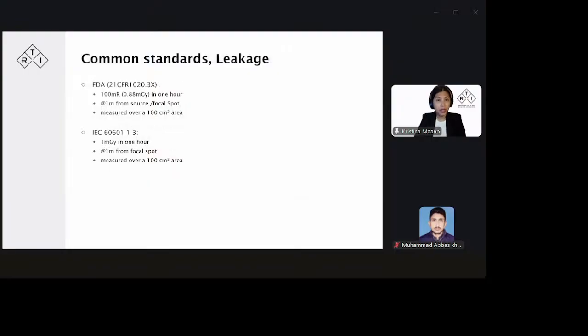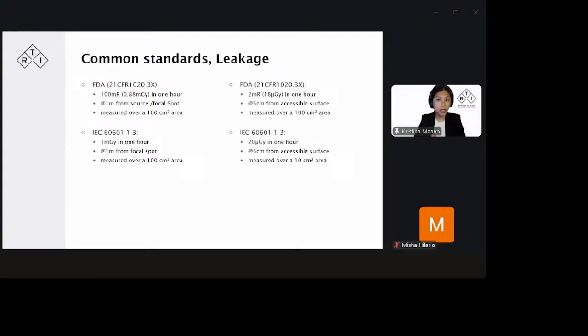All right, so there are standards for leakage evaluation, and two that we are very familiar with, and we have seen them adopted all around the world. First, the IEC, the International Electrotechnical Commission, which says that 1 milligray in 1 hour is the limit. Measurement should be done at 1 meter from the focal spot, and it should be measured over a 100 centimeter square area. This is very similar to the FDA requirements in the US. However, please take note that there are also additional standards when the tube is not discharging. This is done at 5 centimeter from the accessible surface, different from the 1 meter from the source or focal spot. According to the FDA, we do this over a 100 centimeter square area. IEC says to use a 10 centimeter square area.